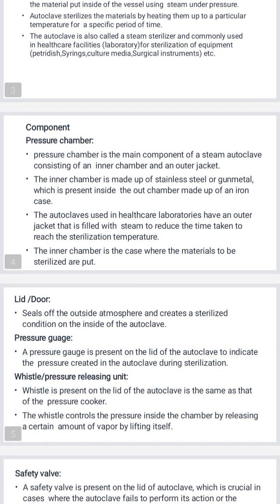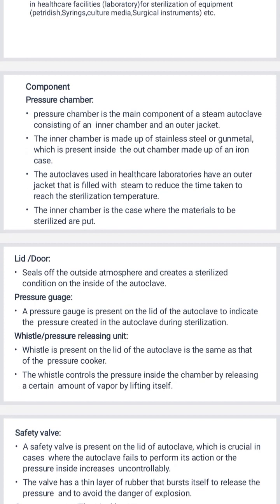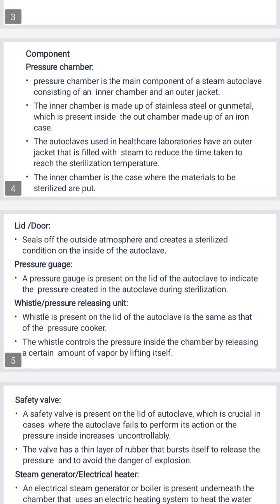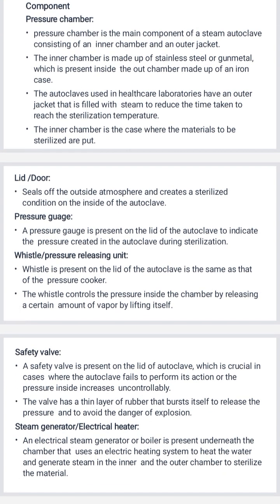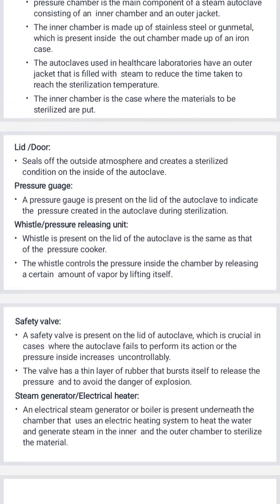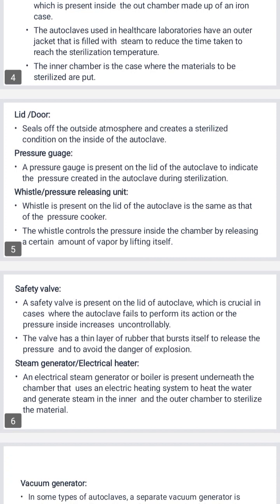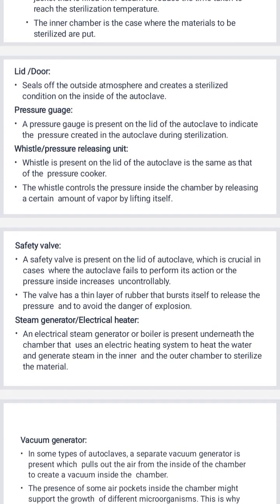The pressure gauge is also a component. The pressure gauge is present on the lid of the autoclave to indicate the pressure created in the autoclave during sterilization. The whistle/pressure releasing unit is present on the lid of the autoclave, the same as that of a pressure cooker. The whistle controls the pressure inside the chamber by releasing a certain amount of vapor by lifting itself. Safety valve: a safety valve is present on the lid of the autoclave, which is crucial in cases where the autoclave fails to perform.